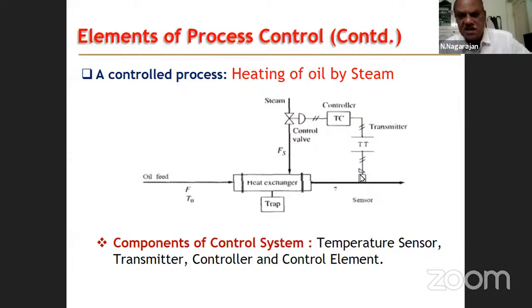There will be a sensor which measures the actual temperature, like a thermometer. Then that measured variable is passed through a temperature transmitter, which converts the measurement into a signal, a pneumatic signal. The signal goes to the controller, and the controller will already have been fed the required value of 150 degrees centigrade. The set point will be there.